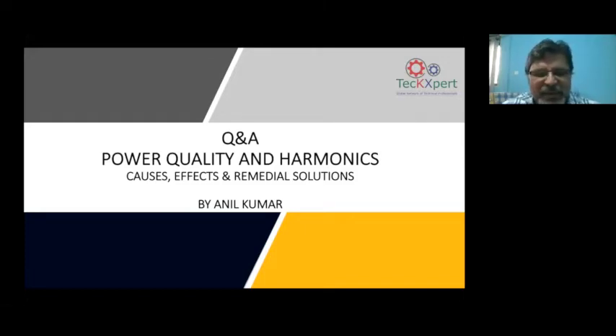Okay, sir. Actually, we have some 600 to 700 LEDs, all 4 feet LEDs. So this EMI filter, we need it, it is available in the drivers, right, sir? See, this sort of failure should not happen, if you ask me. The best thing is to do a study, because by connecting an analyzer we can capture the actual waveform and then give a correct recommendation. I'm quite sure this is a very solvable problem, and it is happening because of the high frequency switching in the LED. Put in an analyzer, capture the waveform, and apply the right solution. That's the right approach. Sure, sir.